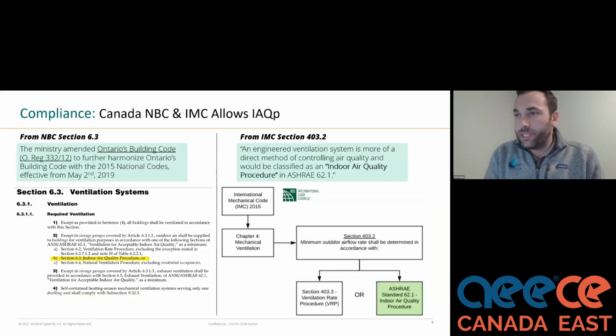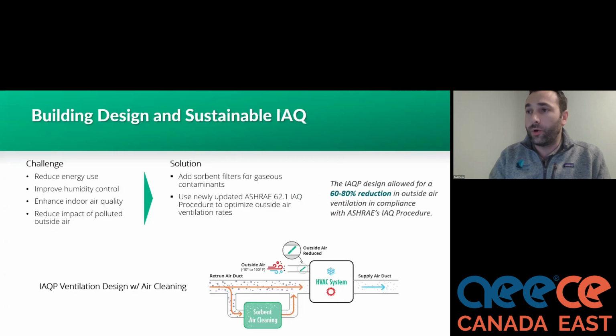required. This has indeed been adopted into Canada's National Building Code, Ontario's Building Code, as well as the IMC 403. So you can see here that the OBC kind of harmonized that building code effective of May of 2019, so relatively recently, calling out the indoor air quality procedure as a valid methodology of calculating your outside air. And indeed, the International Mechanical Code under Section 403 also allows for outside air reduction and calculations using the indoor air quality procedure. So what do we get from that?